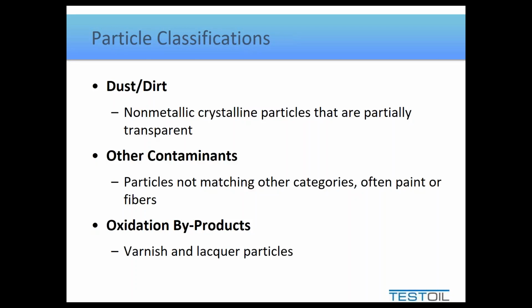As long as the particles, though they may be abnormal by definition, are small and the quantities are low, this is not considered to be much of an issue. When the quantities go up, and especially if the size goes up, this helps indicate the level of severity of whatever mechanism is creating them, and obviously that would be interpreted with much greater urgency.